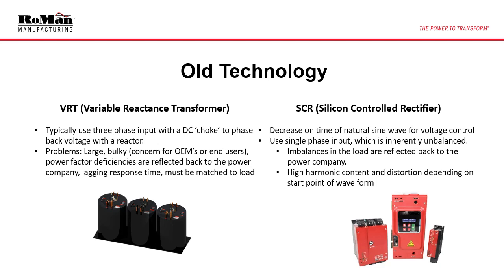SCRs, or silicon-controlled rectifier, also have limitations. SCRs control voltage by decreasing the on-time of a natural sine wave. They typically use a single-phase input, which is inherently unbalanced, and those imbalances are reflected back to the power company. SCRs and VRTs both control voltage by reducing the on-time of a 60 Hz sine wave. This reduced on-time creates inherent inefficiencies in the powering of a furnace.